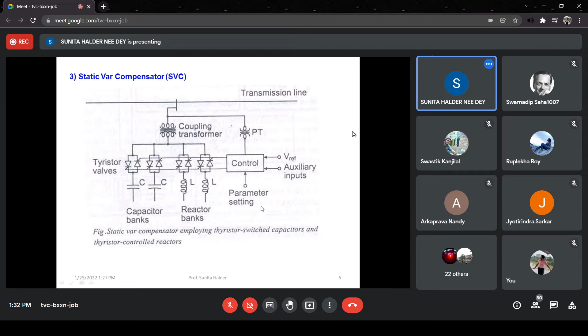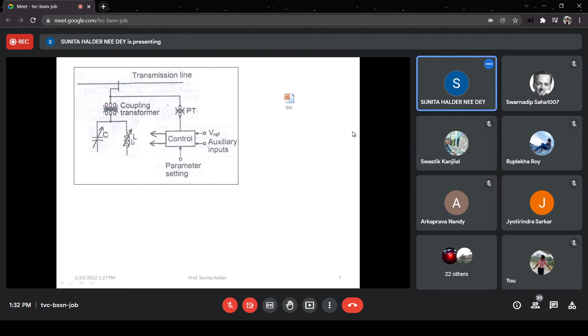So in short, what is a static Var compensator? There is one adjustable capacitor in parallel with an adjustable inductor. Why is the other side not shown? Because this is a per phase representation. This SVC will actually have the three phases. If this is the inductive current, this is the capacitive current. By controlling these two, we can get zero compensation, or capacitive compensation, or inductive compensation. So this is the concept of SVC.